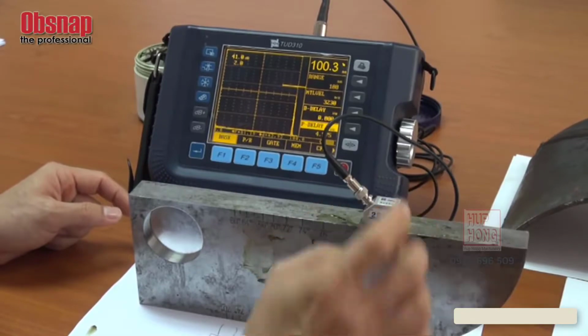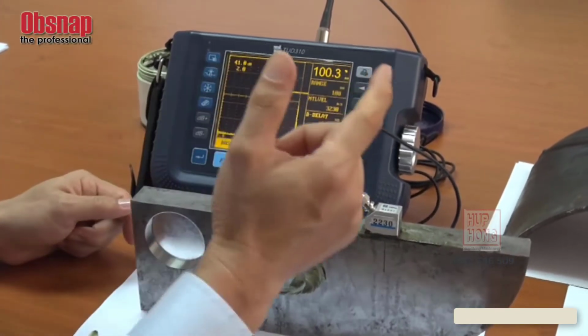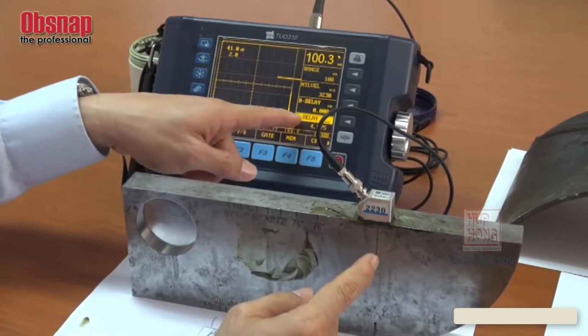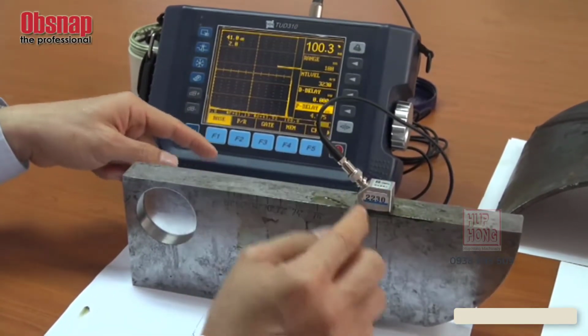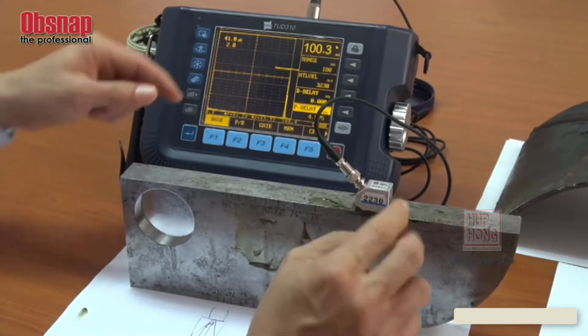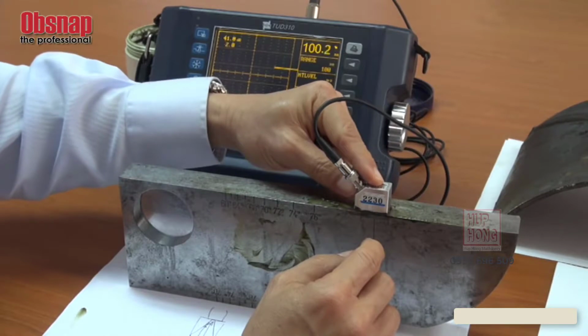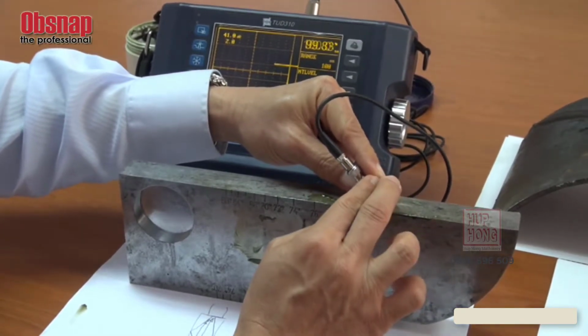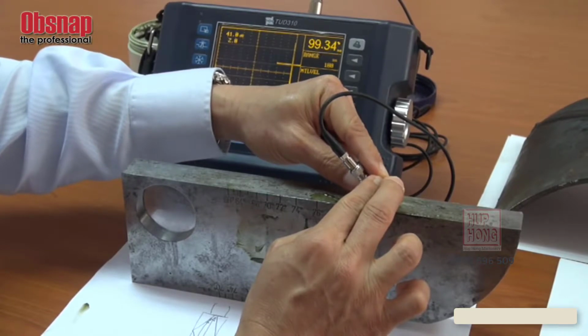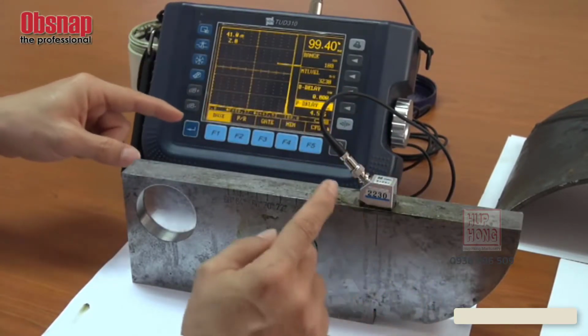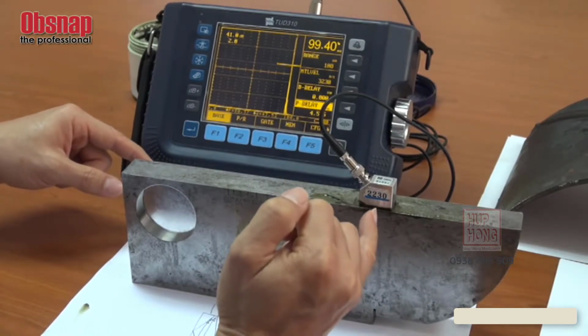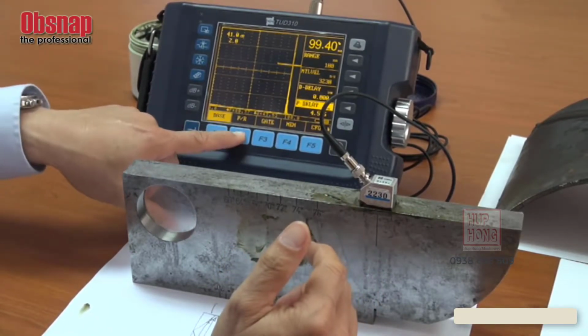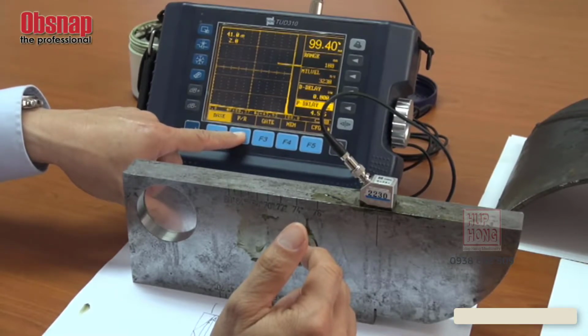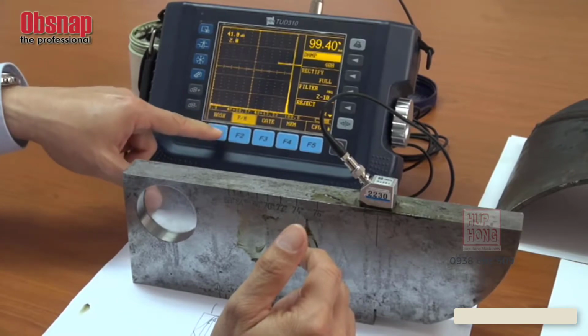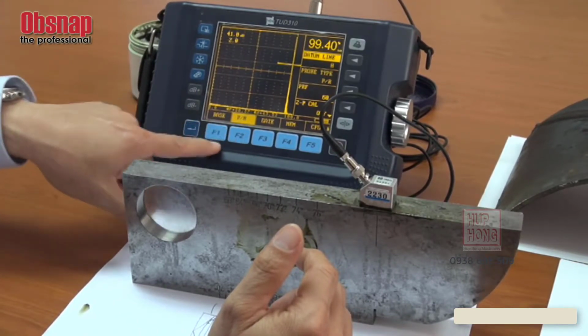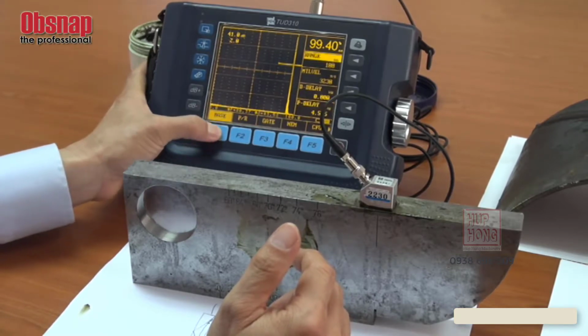Now, there are a few settings we need to do. Number one, probe delay. As I said, I have previously compensated the probe delay. Now, I need to look for the highest pulse, the highest amplitude. Let me see here. Okay, this is the highest amplitude. Then I know where the point is. Hang on. The probe. It's actually at the probe setting, if I'm not wrong. No, it's not at the probe setting. Let me see.